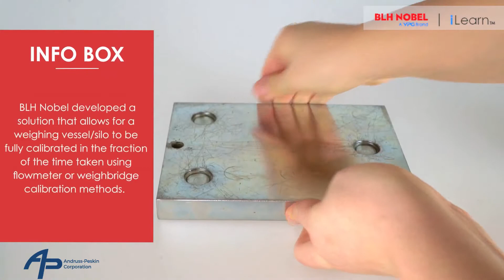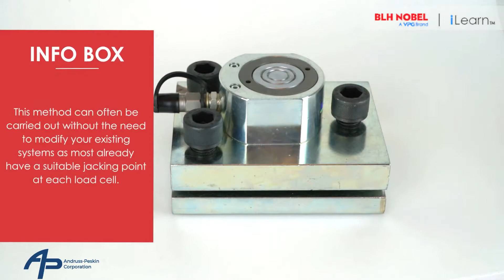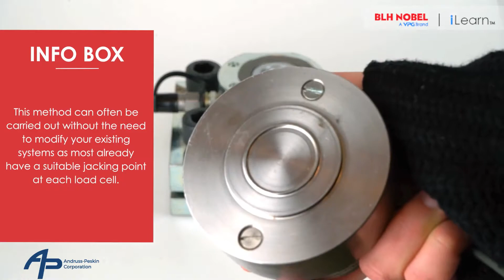BLH Nobel developed a solution that allows for a weighing vessel, or silo, to be fully calibrated in a fraction of the time required using flowmeter or weighbridge calibration methods. This method can often be carried out without the need to modify your existing systems, as most already have a suitable jacking point at each load cell.